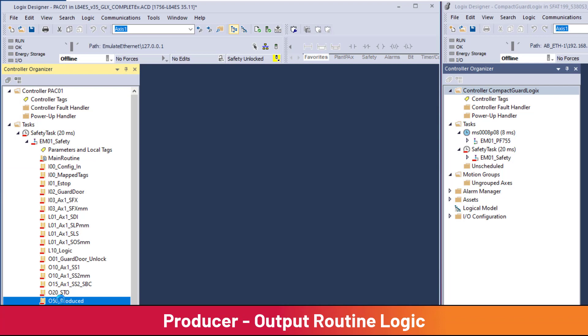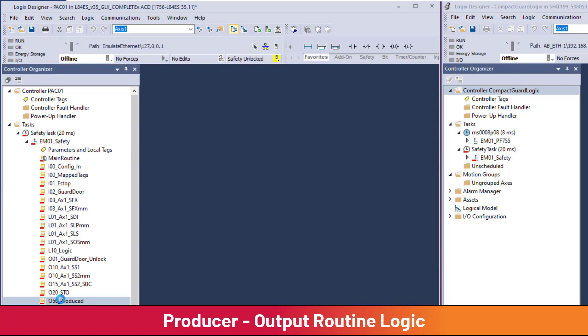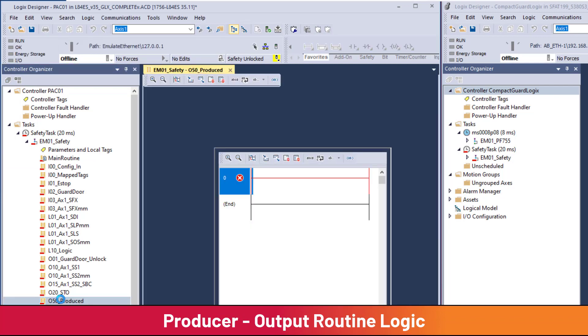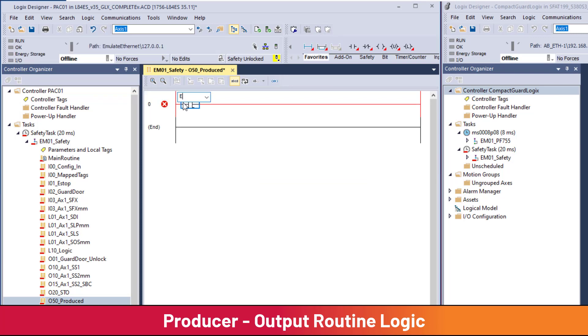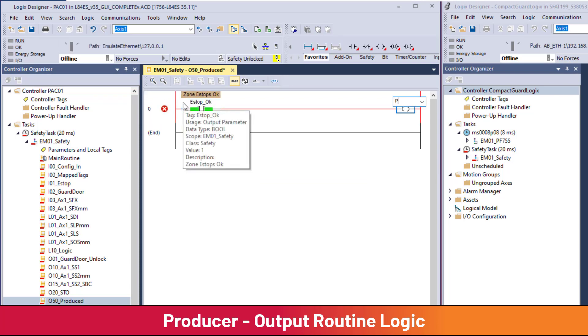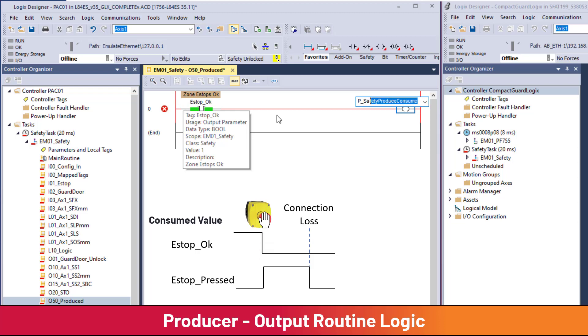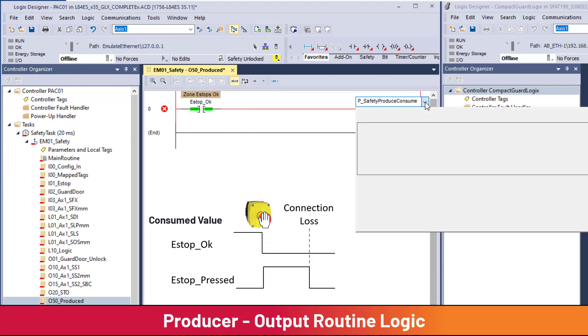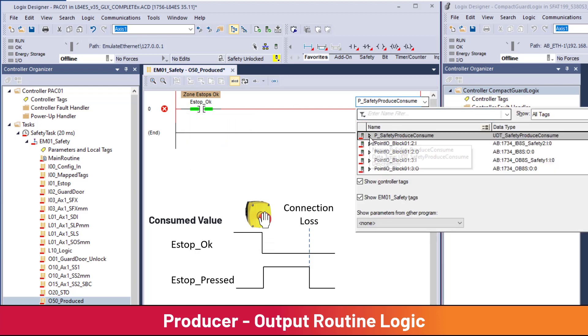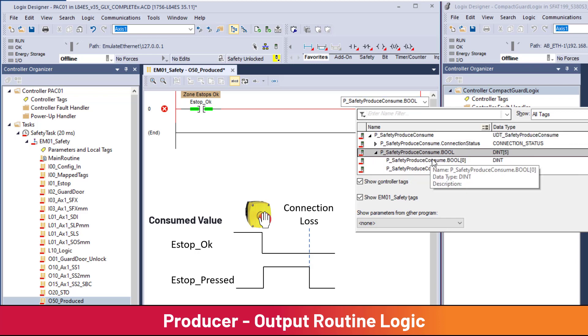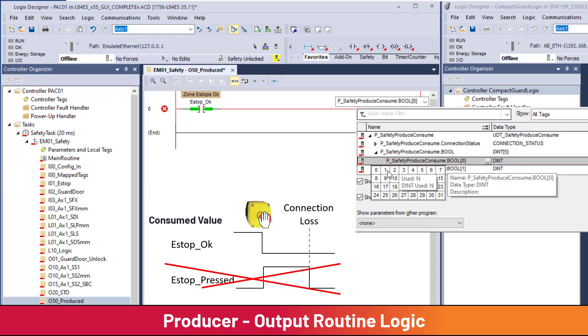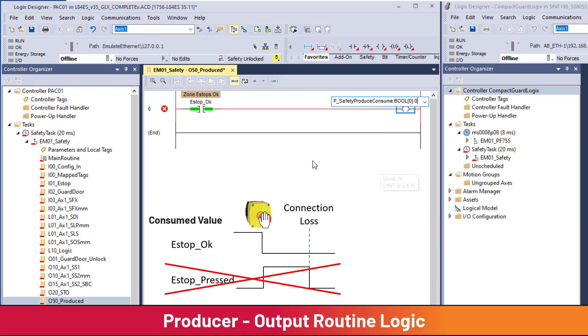In the O50_produced routine, add the data to be produced — in this case, the status of the emergency stop E-stop OK. Attention must be given to sending status where zero equals the safe state. During loss of network connection, all consumed inputs will be zero, so the zero value must control the machine to the safe state.